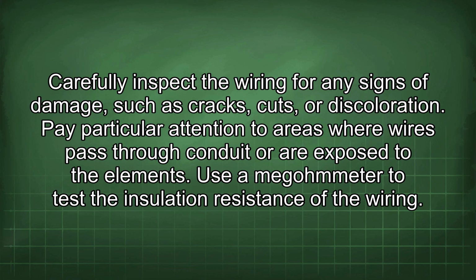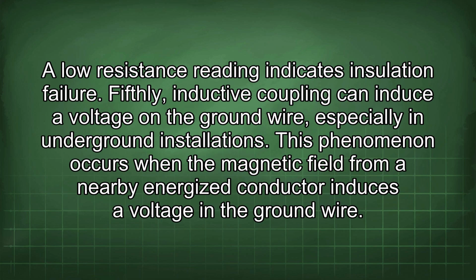Pay particular attention to areas where wires pass through conduit or are exposed to the elements. Use a megohmmeter to test the insulation resistance of the wiring. A low resistance reading indicates insulation failure.